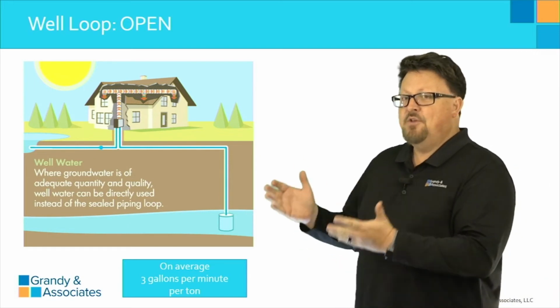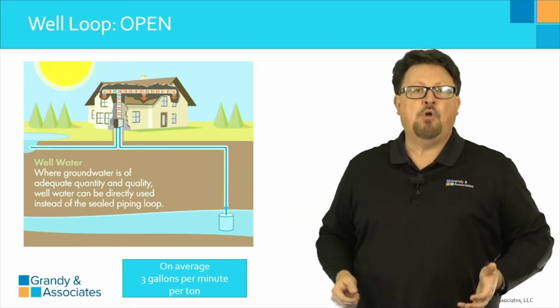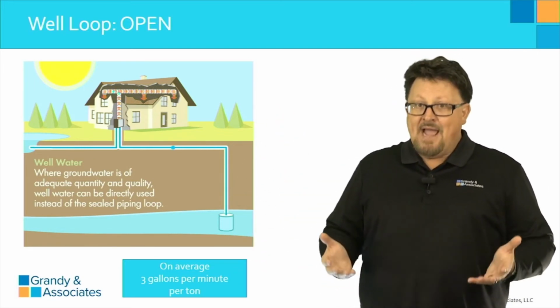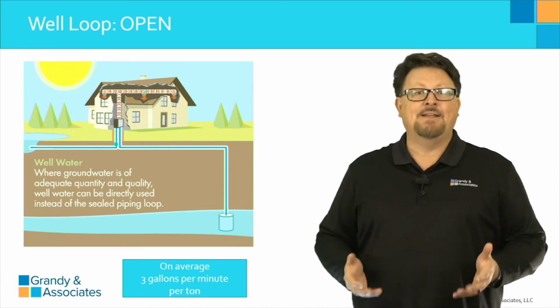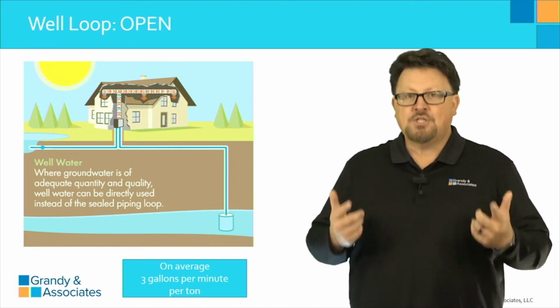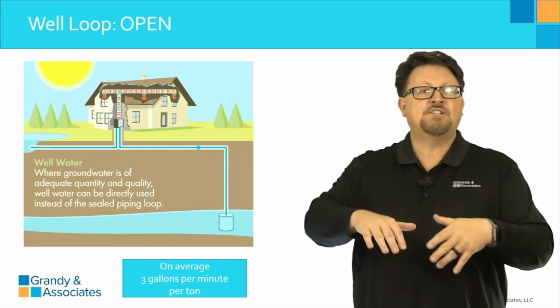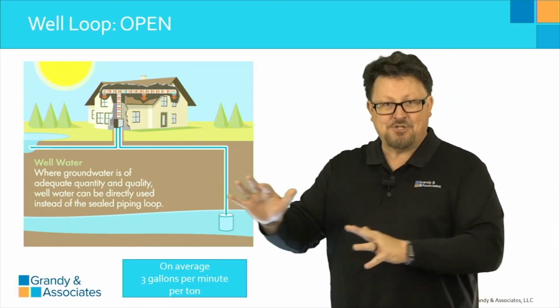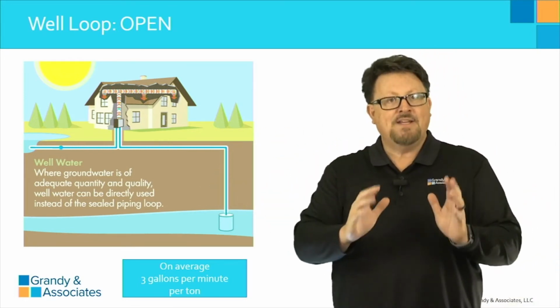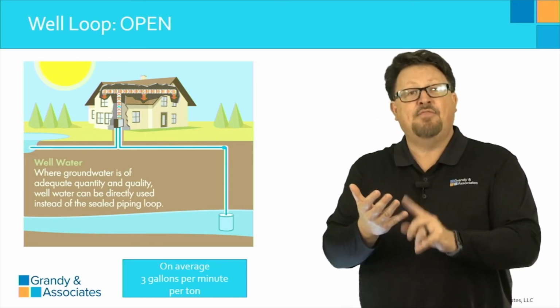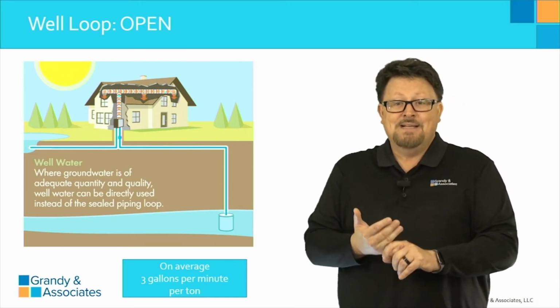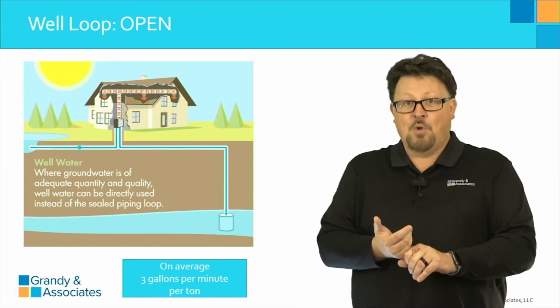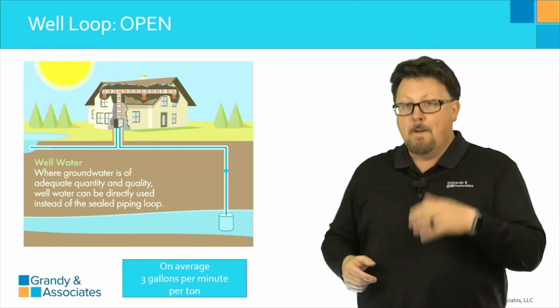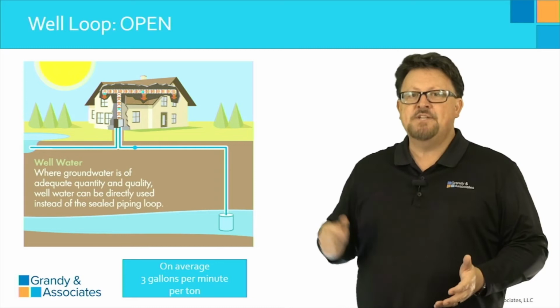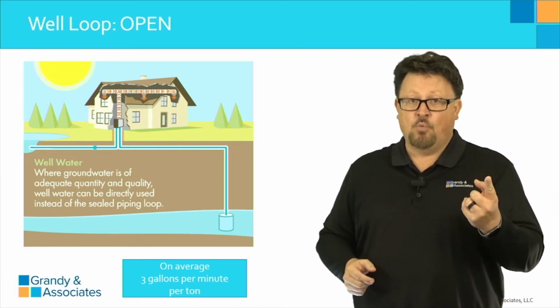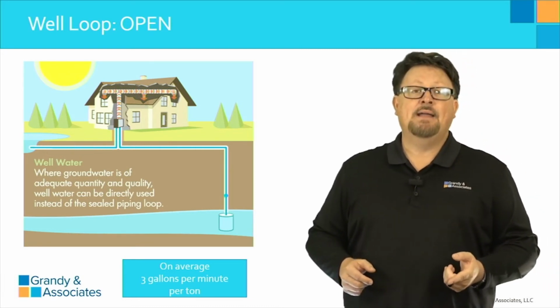One, can the well supply the proper amount of flow? On average you need around 3 gallons per minute per ton. We'll discuss tonnage in a subsequent session of the class, but for our example here, if I had a 3-ton geothermal system, I'm going to need 9 to 12 gallons of flow per minute from this well. So that's test number one: can it supply that amount?